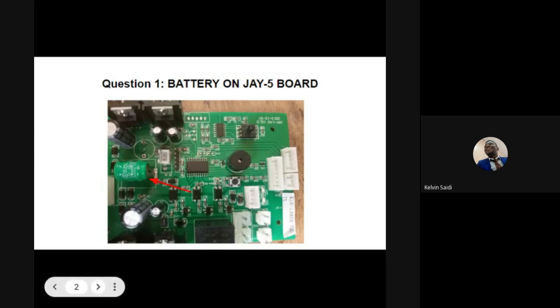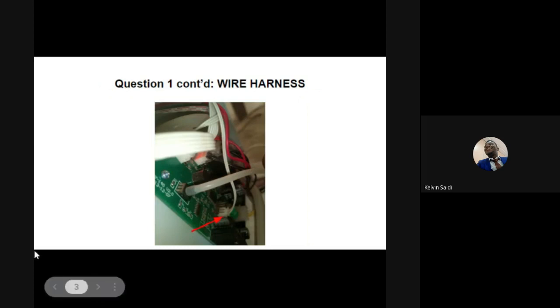Another cause could be that the wire harness going to the switch is broken. Check continuity using a multimeter, and if it is not continuous, replace it, as this could be preventing the alarm from sounding. There were no follow-up questions, so we move on to our next question. Well done to those who sent us questions — it shows you follow through with the Concentrator Talk.